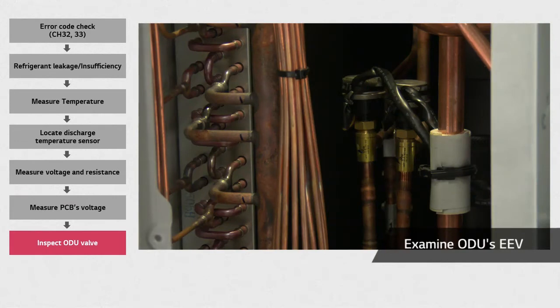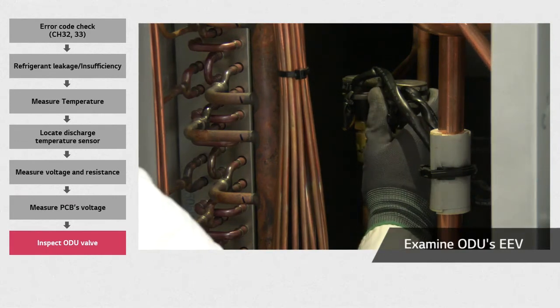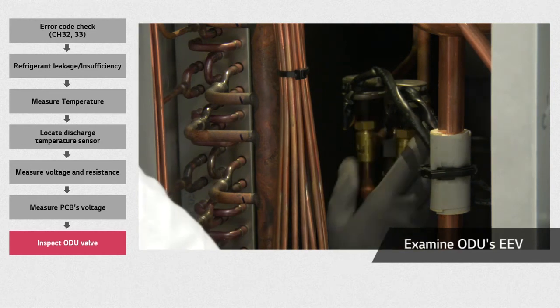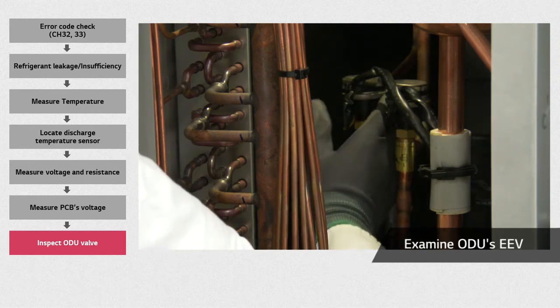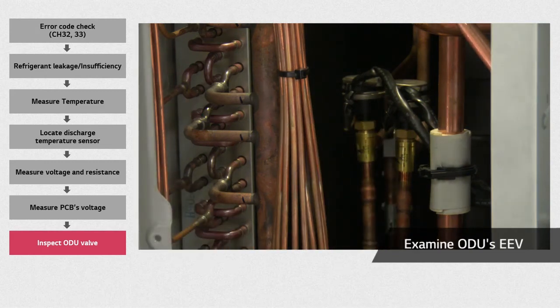Finally, check the outdoor unit electronic expansion valve (EEV). When you reset PCB power, the EEV opens and closes again. If you hold the EEV valve in your hand, you should feel it vibrating.